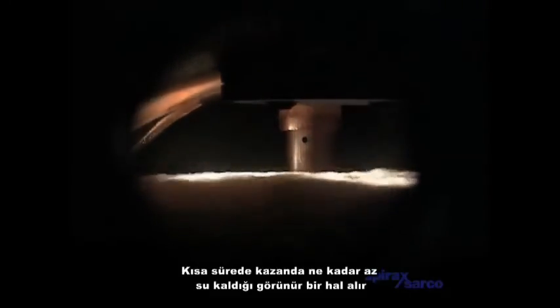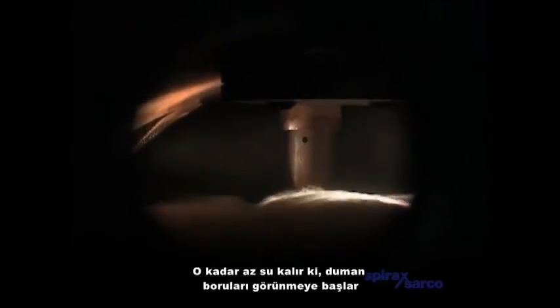This shuts down the burner, and the bubble-charged water drops very rapidly. It soon becomes apparent how little water is left in the boiler. So little, in fact, that the stay bars become exposed. This demonstrates just how important it is to keep a boiler operating within its design parameters and the need for reliable, accurate level probes.